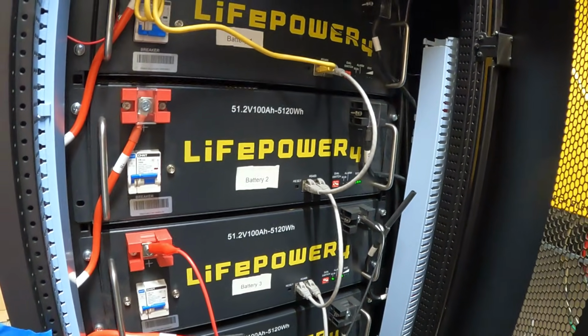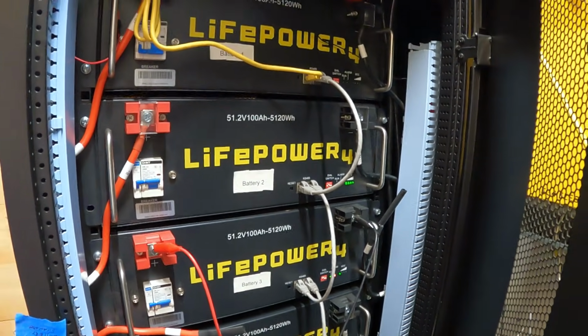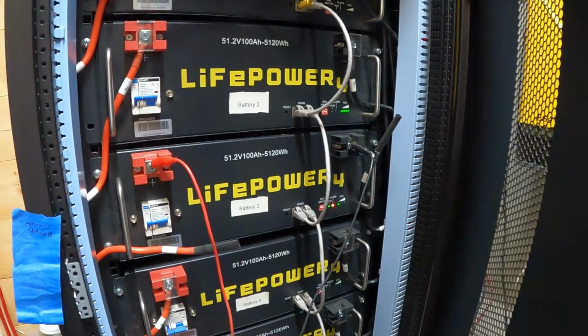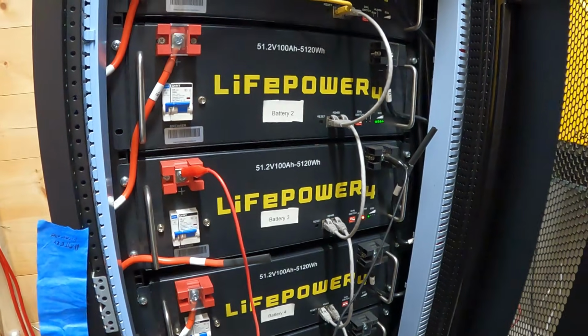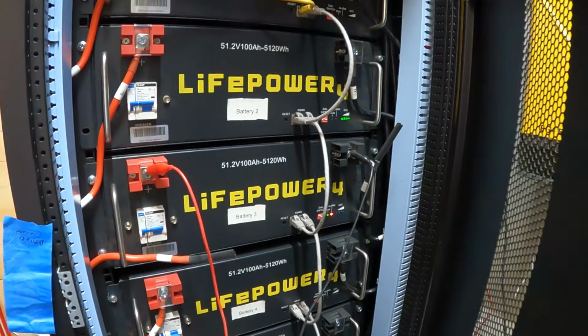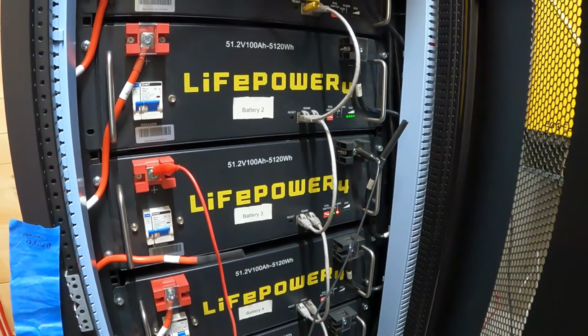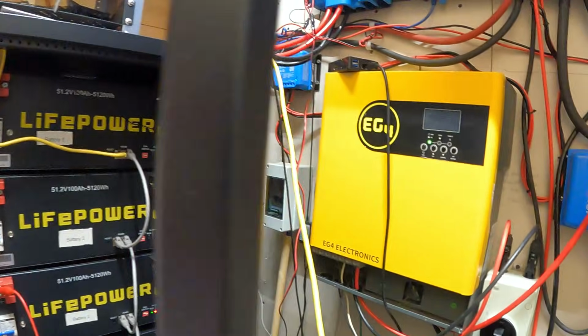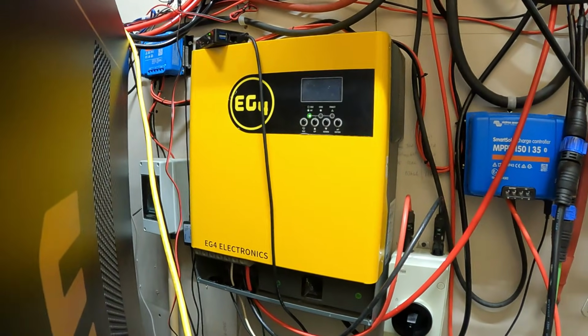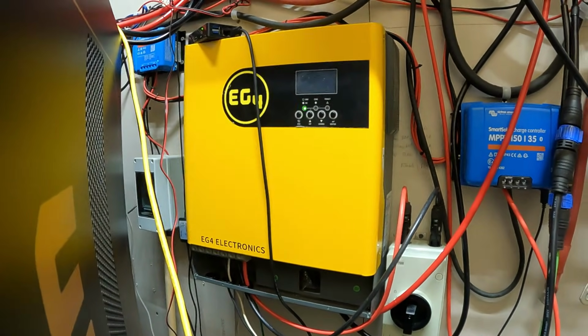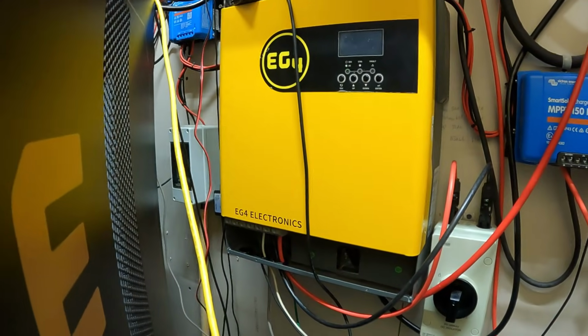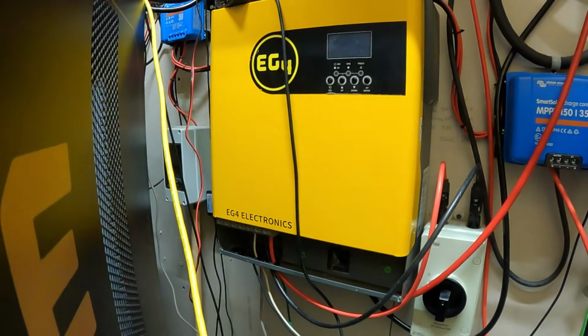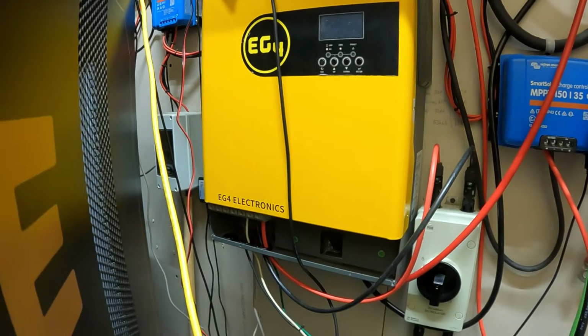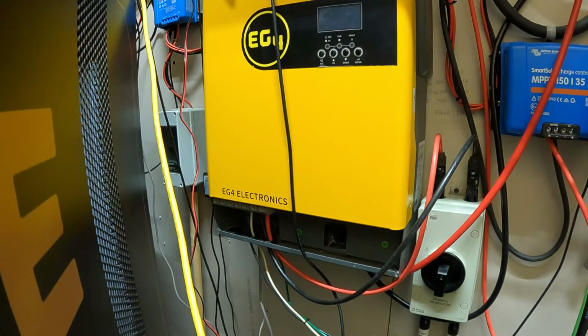So first thing that happened is the state of charge of the stack got low enough, and some of the batteries turned off, and the inverter, which happens to be, I'm just using a little 3000 right now. If the voltage or state of charge gets too low, the inverter turns off. If it can't talk to the batteries because the batteries have turned off, it shuts off.